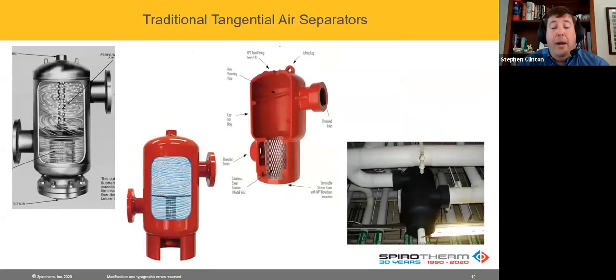And traditional air separators. Now, it's gone from the original iteration that had a small perforated dip tube to the current versions that basically there's really not anything in there. You have the stainless steel strainer, that's really more to catch the cats and the squirrels and the welding rods that get caught in the system. But there's not much there for the air to collect on, to be removed. One thing I remember when I went to pump training early in my career, many years ago, I remember looking at this thinking, why would I design an air removal device that pushes the water in, swirls it around, and removes the water out the bottom rather than the top? Because those bigger bubbles can actually make their way to the top, but it's the small bubbles that don't have the buoyant forces to overcome some of that flow. So I remember even then, even before I knew about Spirotherm, I thought, let's think about that.